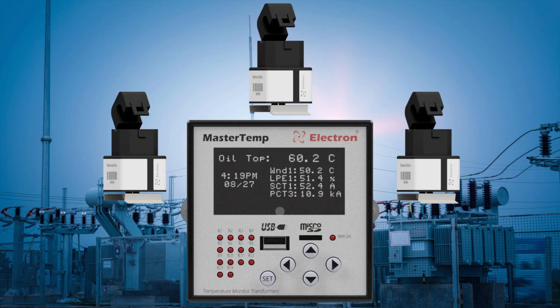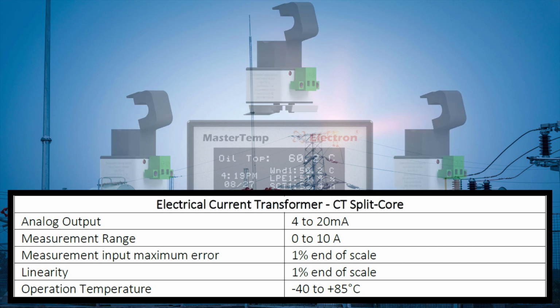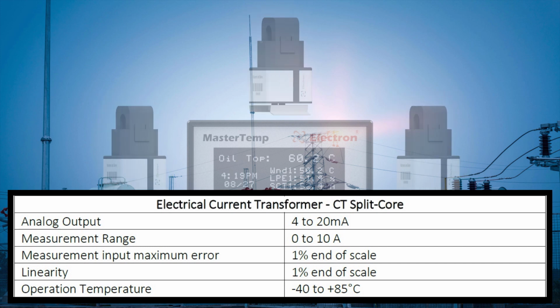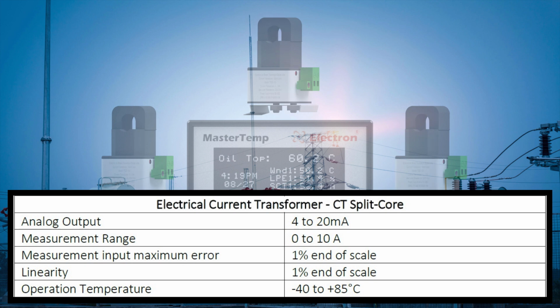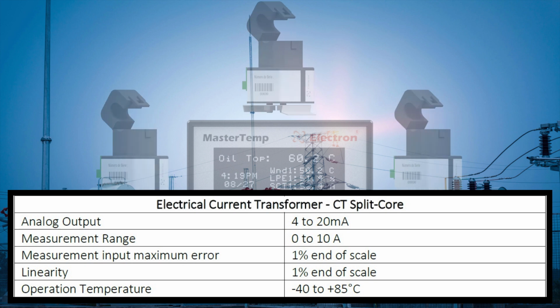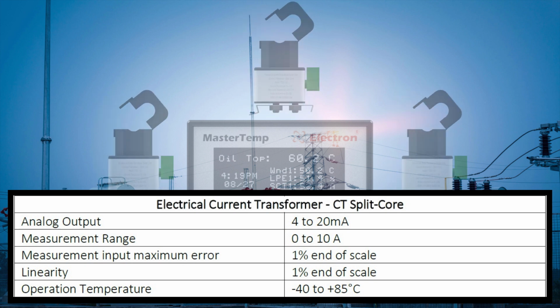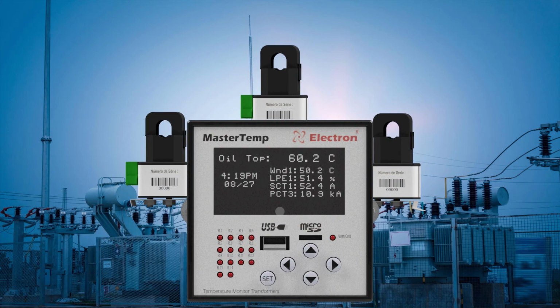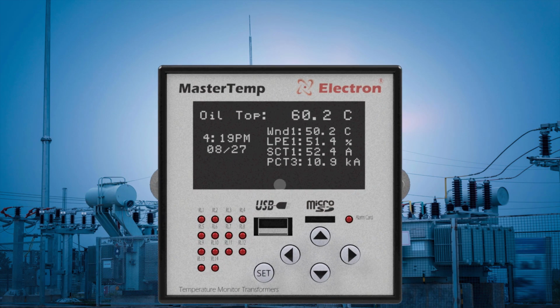The split-core type current transducers have a range of 0 to 10 amperes, alternating current, and convert this analog signal to a standard of 4 to 20 milliamps and guarantee quality, precision, and safety of the signal for great distances.